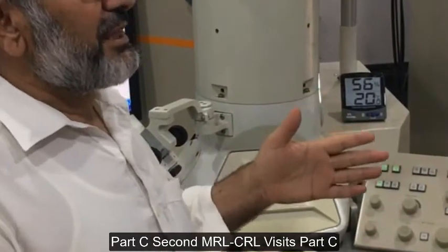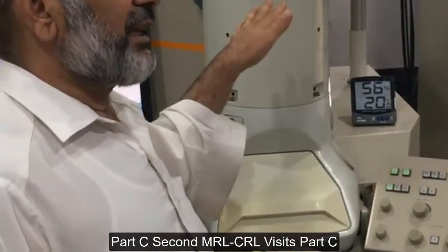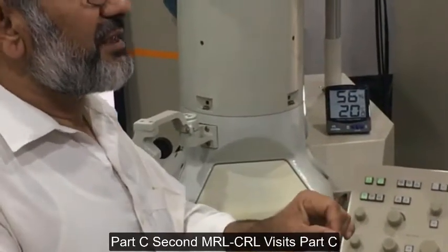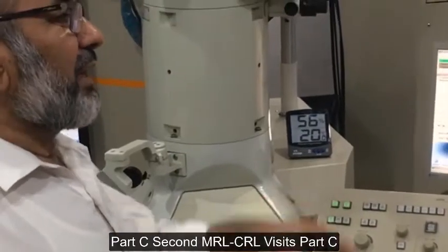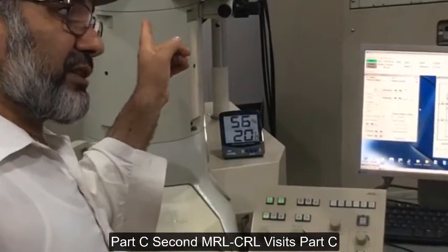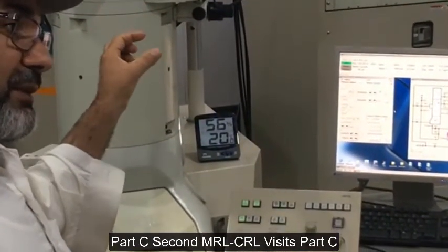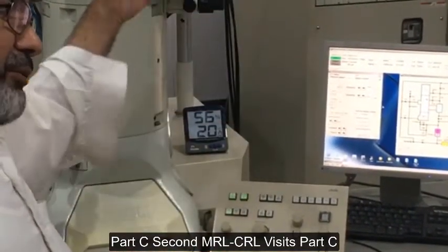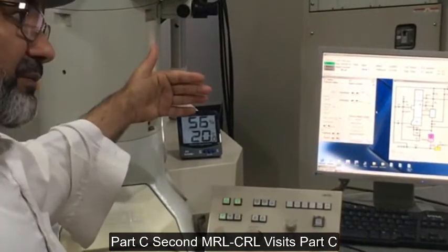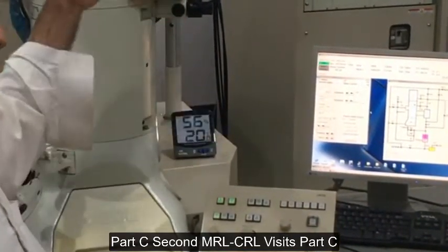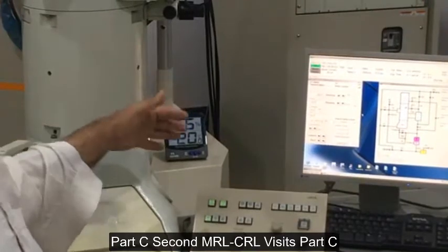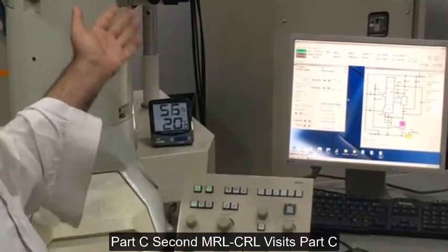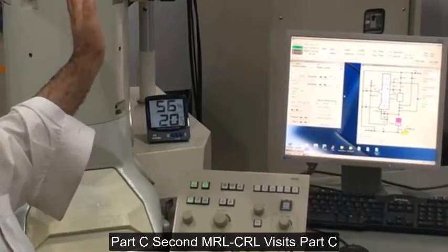The interplanar spacings are known there. So when you take an image, from the image you have distances in centimeters, and the actual distances are in angstroms. So you calibrate the machine so that these many centimeters are equivalent to these many angstroms. Then when you put in an unknown sample, you say that if this is 2 centimeter, it means it is 3 angstrom or 4 angstrom. That is the calibration of the image.